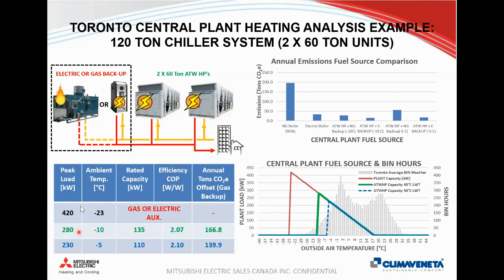So even using the heat pump down to -10 would offset about 166 tons per year based off this load profile. The load profile will dictate what the results will be. Even at -5, you might think our heat pump's not meeting our full design temperature, but it doesn't really need to, because you can still see significant carbon savings, kilowatt hour savings, and cost savings that we'll get into shortly, with about 140 tons offset per year.